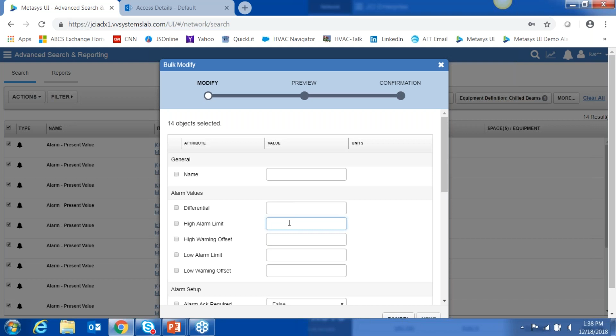Let's take a look at the zone temperature points and the alarm extensions. Let's search on those. From this screen I could modify all of the high and low alarm limits for all of the zone temperature points I filtered on for this particular floor. So I've saved maybe dozens to hundreds of mouse clicks by performing a bulk modify of those alarm limits, simply by using the power of our spaces and equipment definitions and our new Advanced Search and Reporting feature.